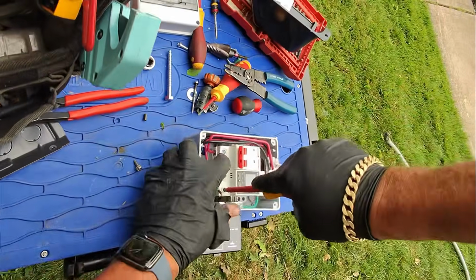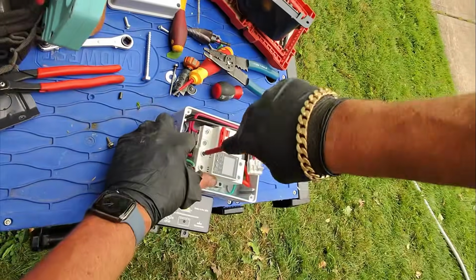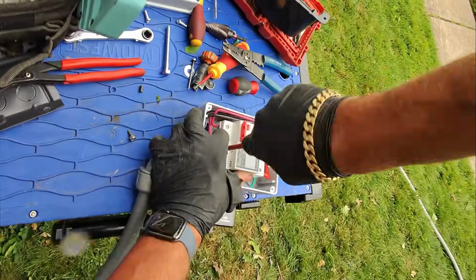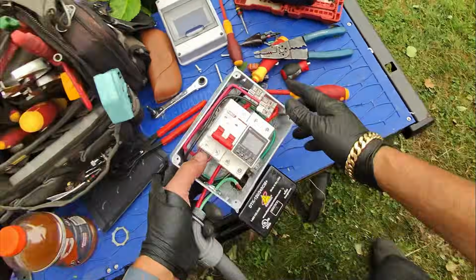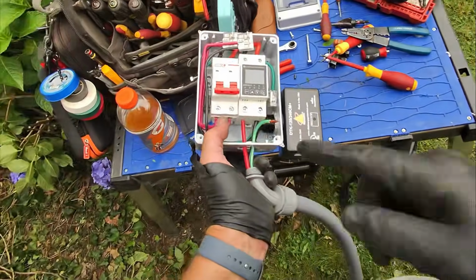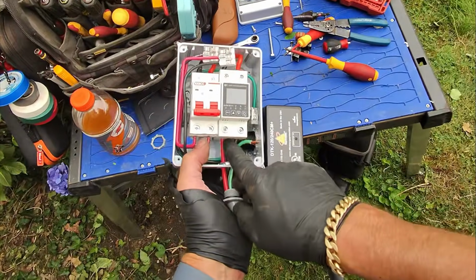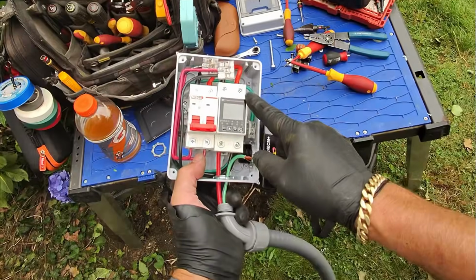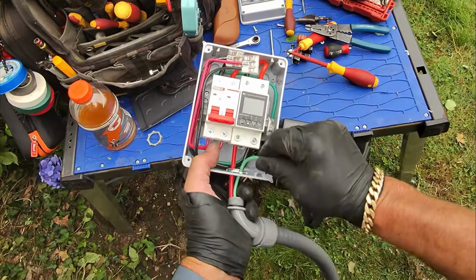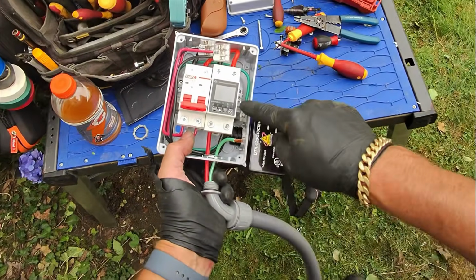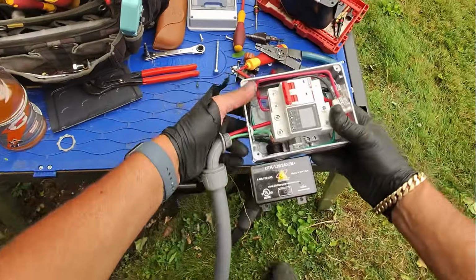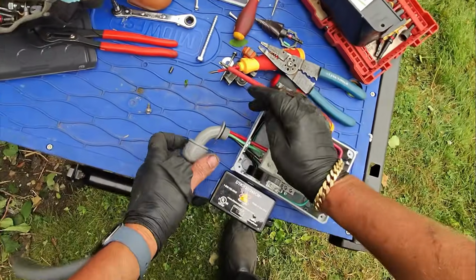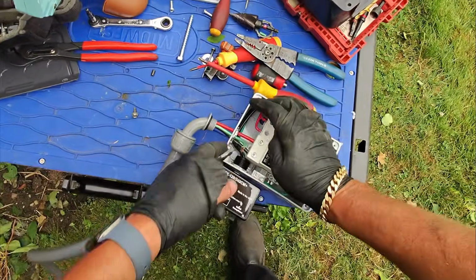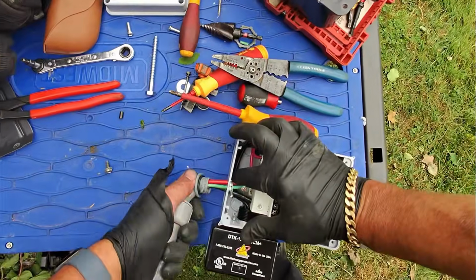So what's great about my terminals on my outlet side is that I can fit 8 to 12 gauge wire on the outlet side of the power monitor. Okay, our ground, which is 10 gauge, will connect there no problem. And all we got to do now is basically get rid of that slack, push this in.